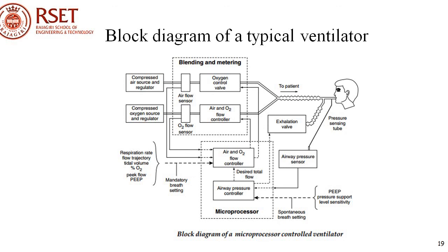Ventilator machine consists of two separate but interconnected systems: the pneumatic flow system, that is the upper part of the block diagram, and an electronic control system, which is the lower part. The pneumatic flow system enables the flow of gas through the ventilator. Oxygen and medical grade air enter the ventilator at some 3.5 bar pressure through built-in micron filters.